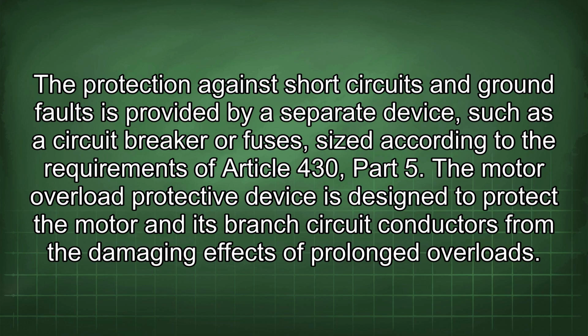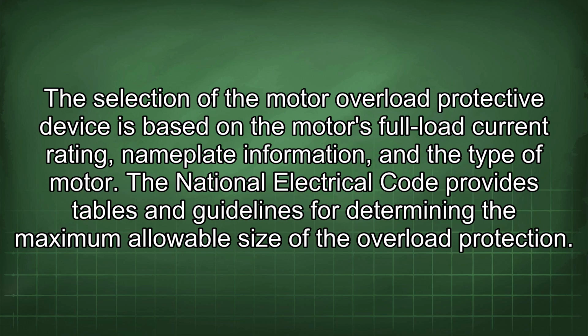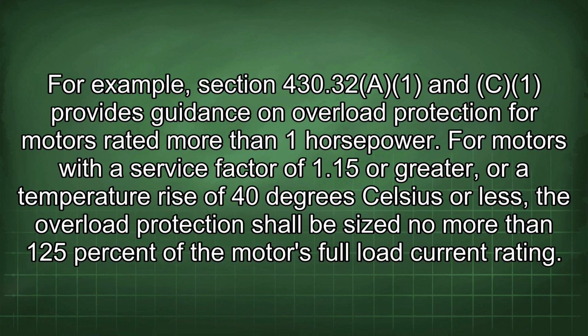A motor overload protective device is designed to protect the motor and its branch circuit conductors from the damaging effects of prolonged overloads. The selection of the motor overload protective device is based on the motor's full load current rating, nameplate information, and the type of motor. The National Electrical Code provides tables and guidelines for determining the maximum allowable size of the overload protection. For example, Section 430.32(A) of the Code provides guidance on overload protection for motors rated more than 1 horsepower.